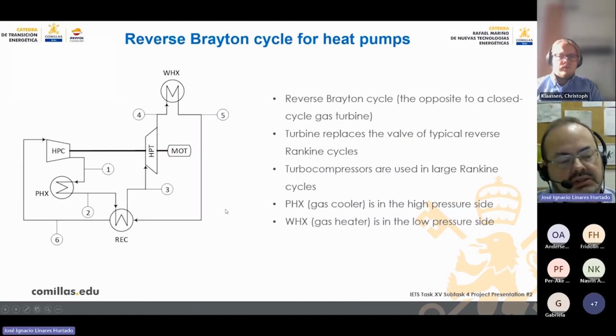Okay, which is the scheme of the layout of this heat pump? Firstly, this is the basic layout with a compressor, a turbine, and a motor to drive the equipment. We have the waste heat exchanger to recover the heat from the source, and the product heat exchanger to release the heat to the demand. This is the recuperator, in order to move the excess heat from the demand to preheat the working fluid in the suction of the compressor.